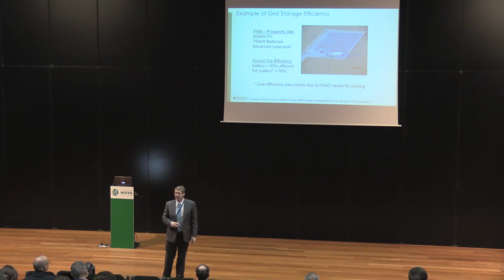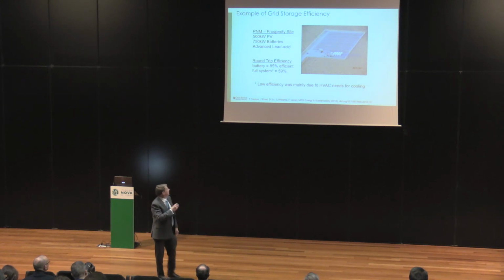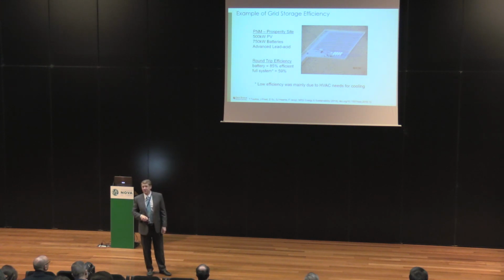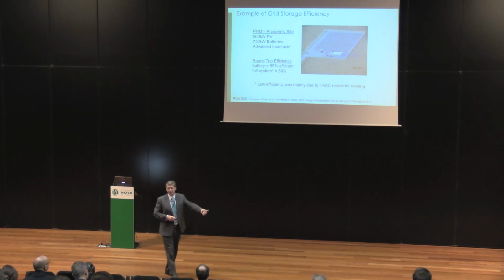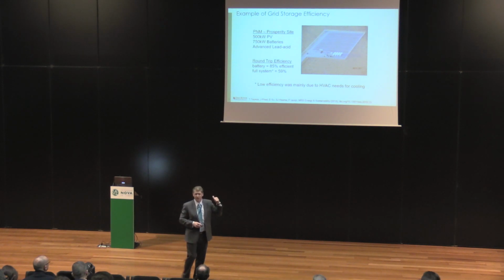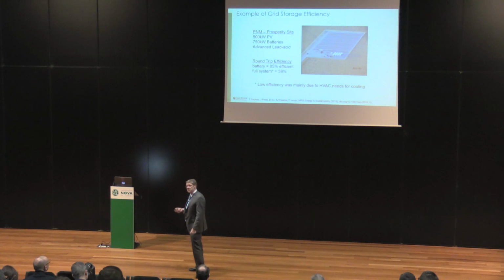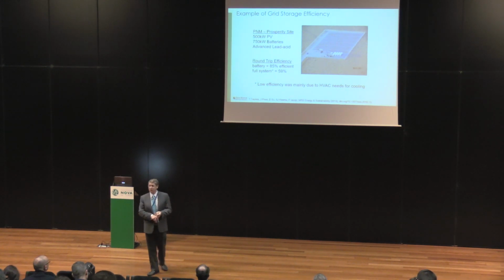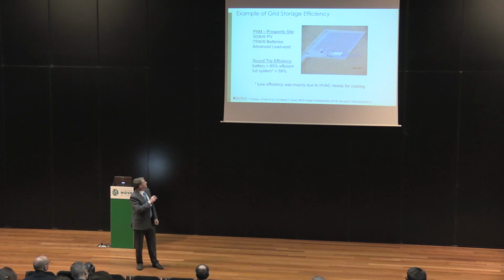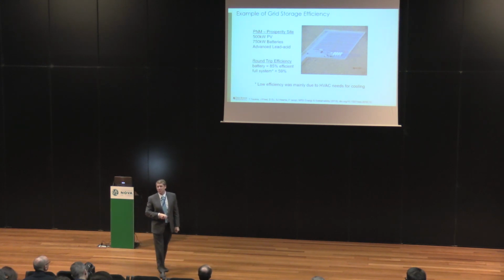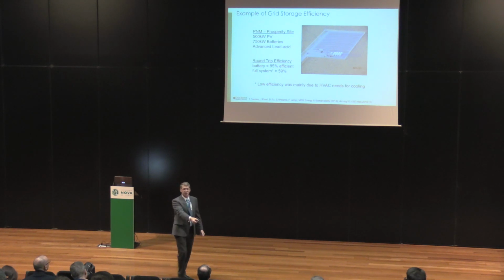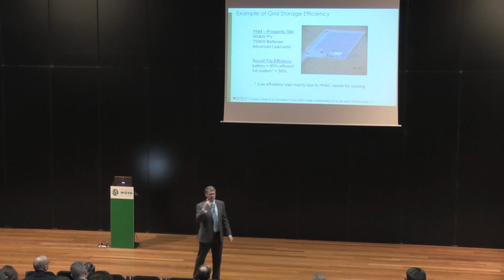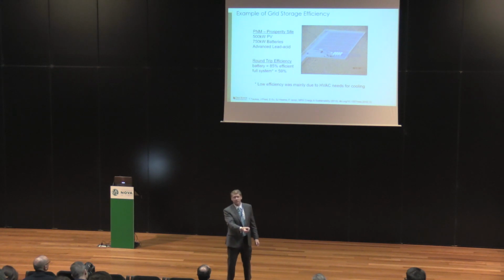Well, the downside is round-trip efficiency. The batteries themselves, these lead-acid batteries, are only 85% efficient—for every electron you put in, you get 0.85 electrons back out. However, the full system, when you actually account for all the air conditioning, because you need to keep the batteries cool, you need to keep the power electronics cool, which is actually one of the critical pieces, your efficiency drops down to only 59% efficient round trip. And that's assuming that you're putting the electrons in and pulling them almost immediately back out. The longer they're stored there, the less value you derive from the system.